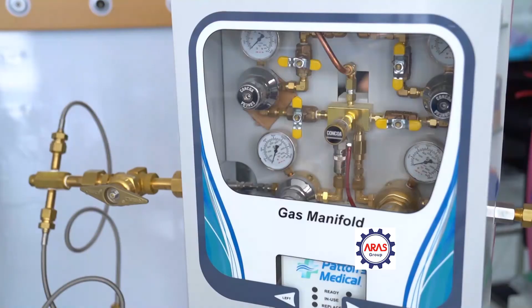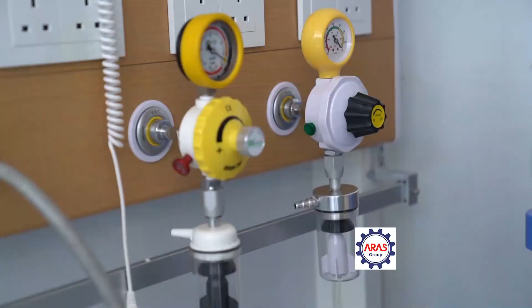Then we are talking about how to connect the cylinders. Same thing, you should know the connection of the valve, the connection of the manifold, and the type of gases we are using. If you are connecting oxygen, nitrous oxide, air, and those connections are not correct, the patient will die, or our service will be completely interrupted. Therefore, training is definitely very important.